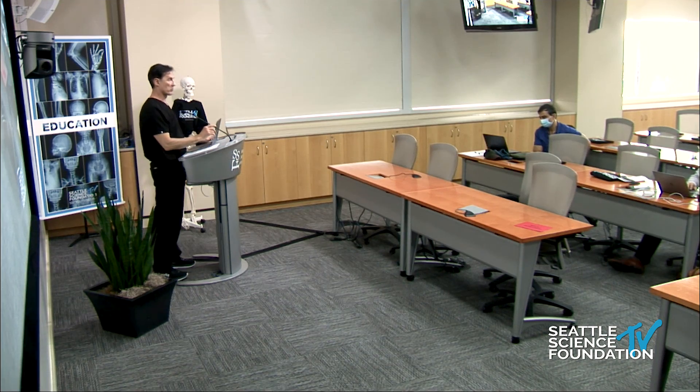The implantation of DRG is a little more delicate than it is with spinal cord stimulation. The quadrupolar leads are thin — like angel hair pasta compared to large spaghetti. This is hooked to an IPG that has four ports. When planning the procedure, whether you're putting it at L1, T11, or S1 and S2, the technique is more difficult than spinal cord stimulation, but it's not that difficult — it's just different.